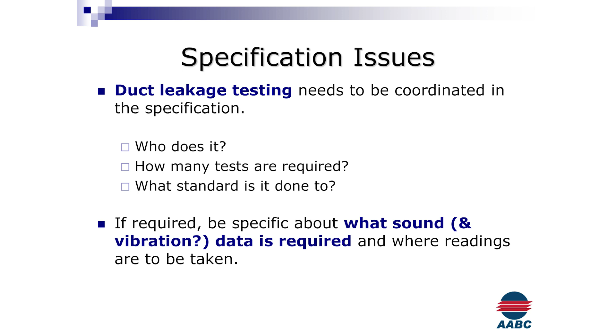Specification issues. Duct leakage testing needs to be coordinated in the specification. Who does it? How many tests are required? And most importantly, what standard are we testing it to? Is it SMACNA? Anybody know? That's the question, right? Whenever I get into the GC, I say, all right, we're going to do it to the SMACNA standard. This job is doing all the other installation per the SMACNA standard, and then they turn the table on us and go, oh no, we don't want that—we want a 1% leakage. Well, your class and your ceiling that you specified for the ductwork isn't going to handle a 1%, right? And they have an unrealistic expectation of what we are able to do and accomplish with that duct leakage test.